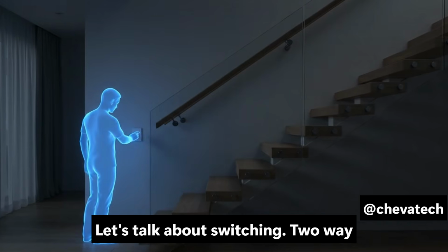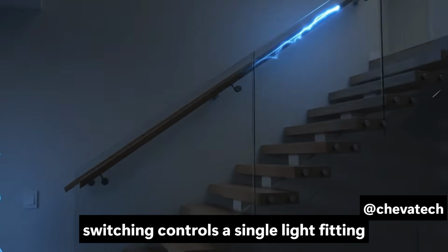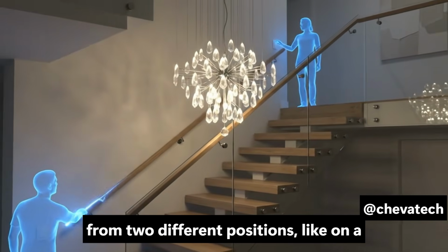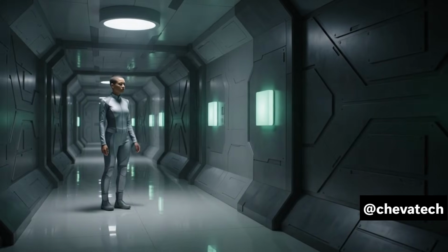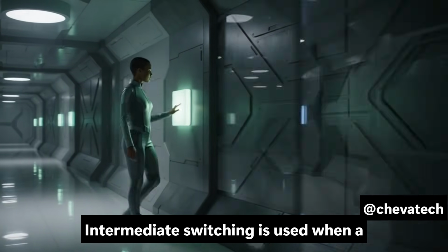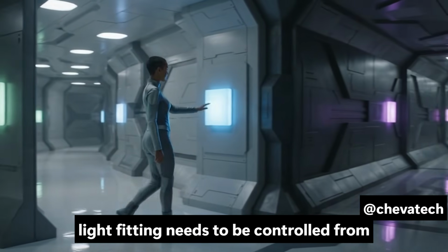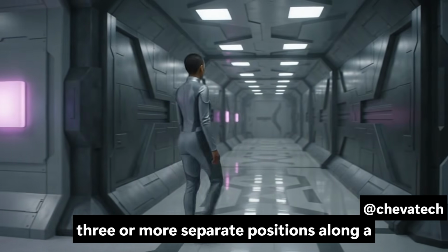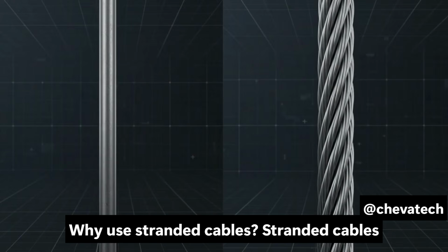Let's talk about switching. Two-way switching controls a single light fitting from two different positions, like on a staircase landing. Intermediate switching is used when a light fitting needs to be controlled from three or more separate positions along a corridor. Why use stranded cables?